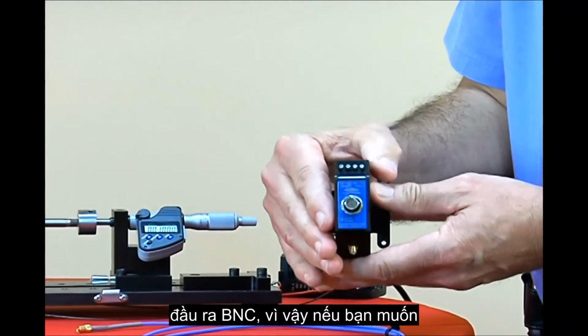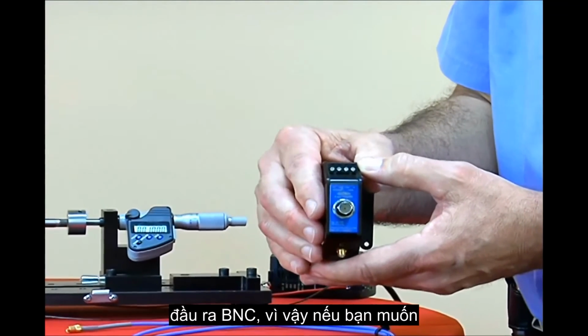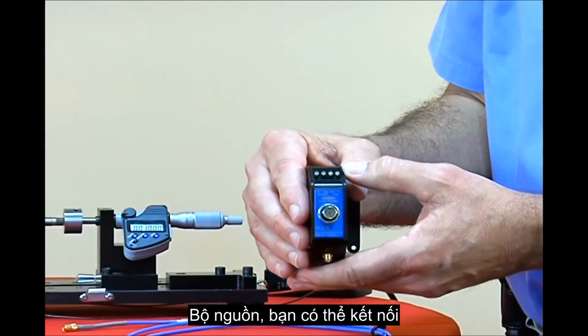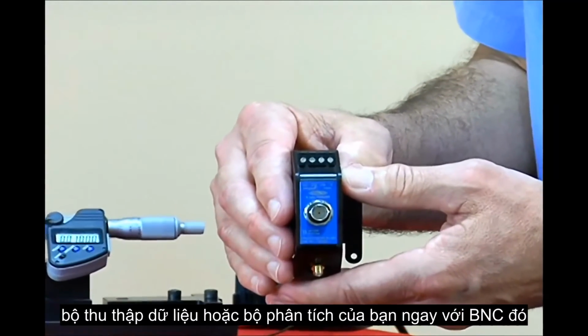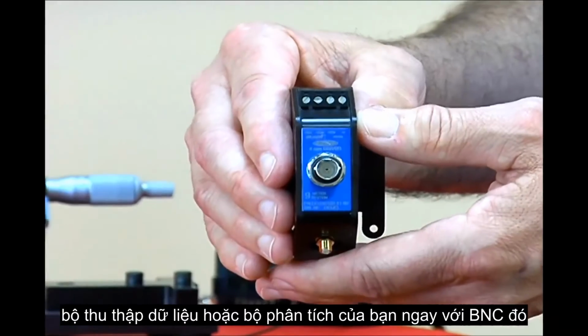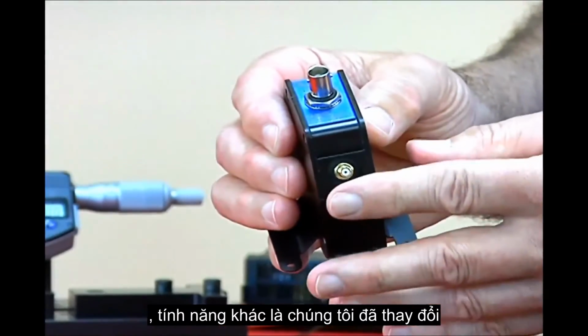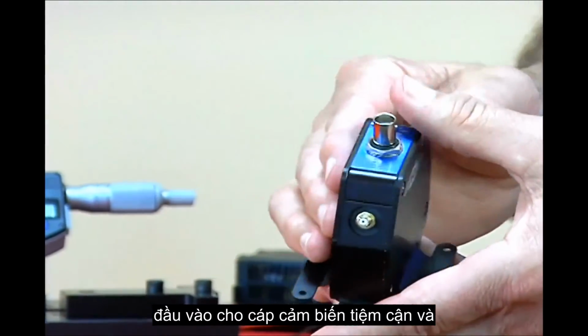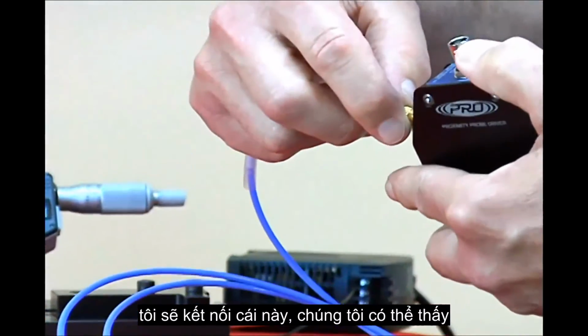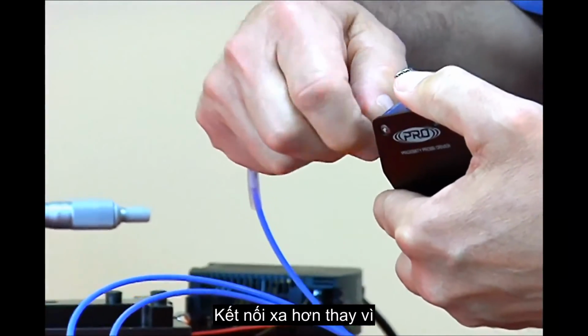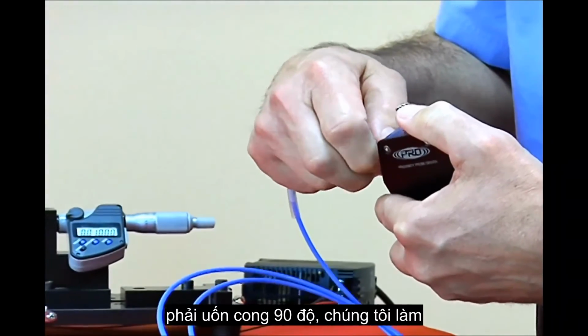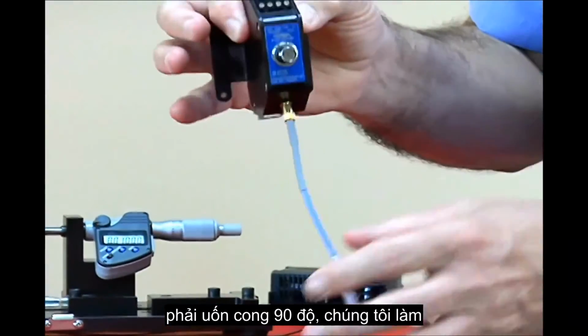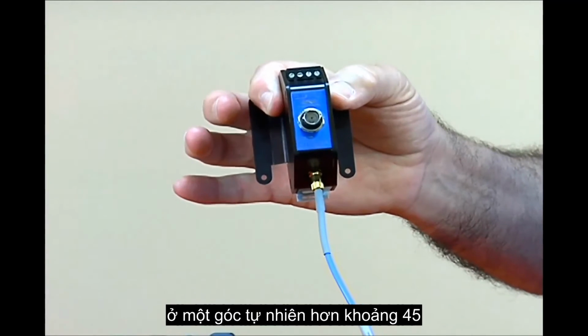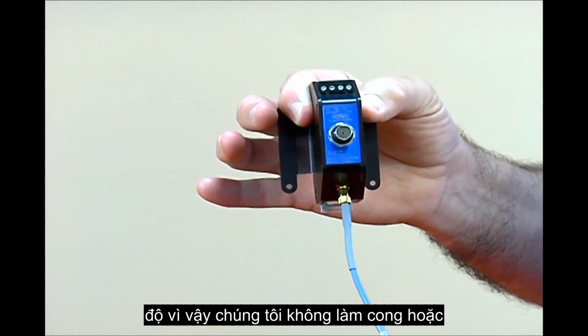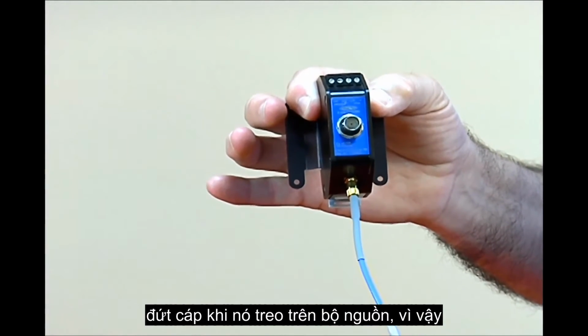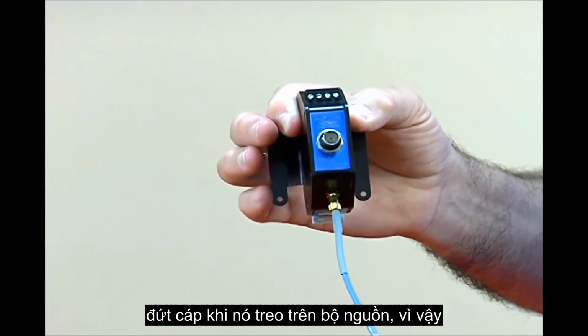We've maintained our buffered BNC output, so if you'd like to do portable data acquisition from the driver, you can connect your data collector or analyzer right to that BNC. The other feature is we've changed the input for the proximity probe cable — let me connect this so we can see how it falls away better now. Instead of having that sharp 90-degree bend, we come off at a more natural angle of about 45 degrees, so we're not bending or breaking the cable as it hangs from the driver.